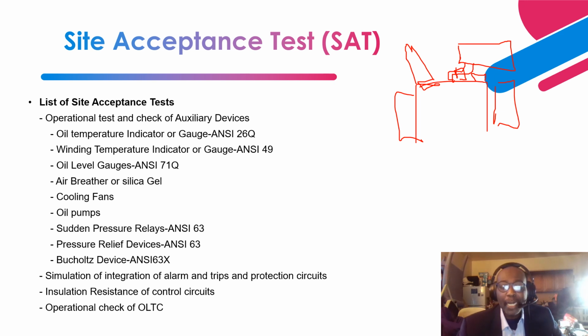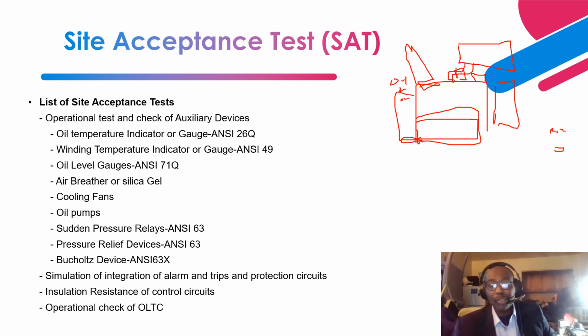The only components that will remain are the auxiliaries: the oil gauge, the temperature gauge, the winding temperature gauge, the oil level gauge, and also the control box, the cubicle where all the wiring interface from the transformer comes in, and from here it goes to an RTU to your SCADA system, right? That one will be kept on the transformer, but it's going to be padded to prevent damage during transportation. Then the oil in the transformer will all be drained and put in drums.